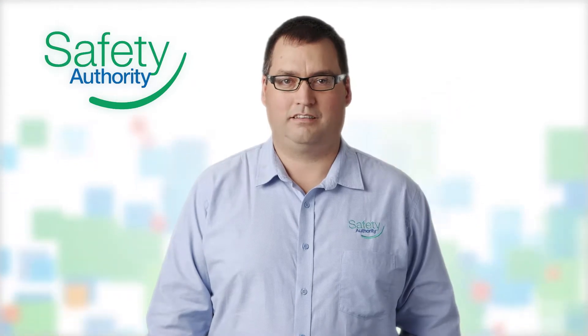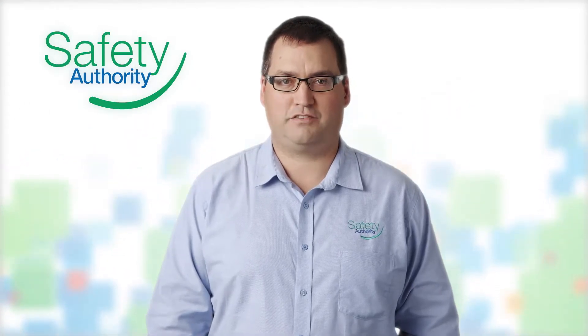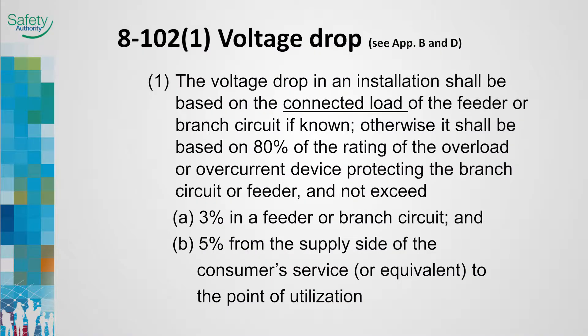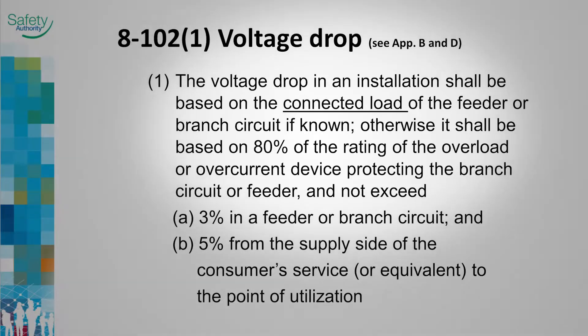Welcome to Section 8, Circuit Loading and Demand Factors. Let's review the changes for 2015. Rule 8102, Sub Rule 1 now requires the voltage drop to be based on the connected load rather than the calculated load.